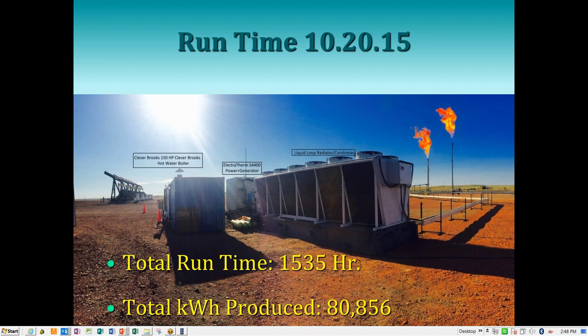The challenge I've understood from a microturbine standpoint, or any prime power standpoint, from talking to customers that own different types of prime movers, including fuel cells and engines, is that the gas treatment is the tough part. The BTU content and the liquid content vary all over the place, and that becomes an issue for something that wants to maintain constant speed. With the boiler, like I said, the boiler just sits there, and we don't care if it gives us a little less or a little more hot water flow. Our set point on the boiler was about 232 degrees, and as the flare does its thing, the boiler takes care of that. So we have a buffer between us and the flare gas.